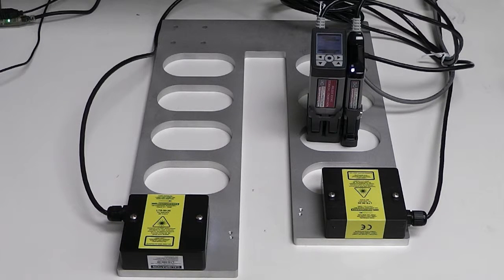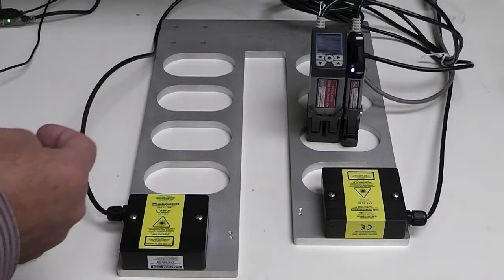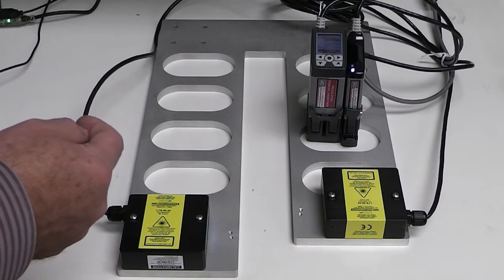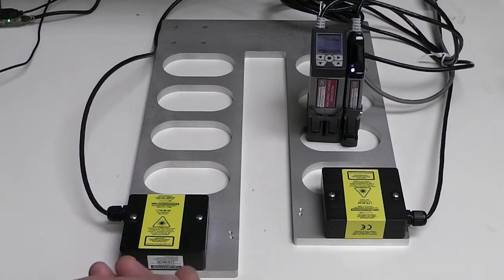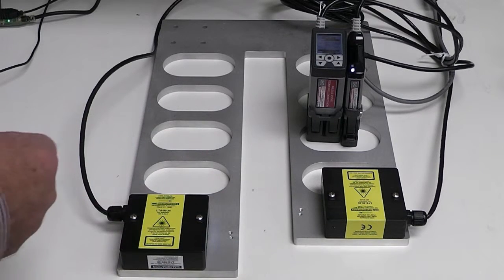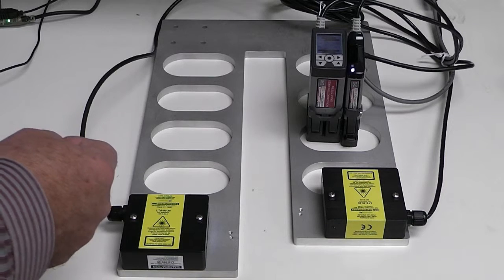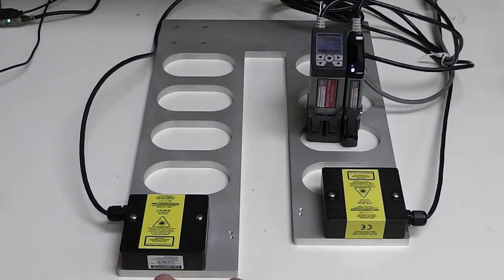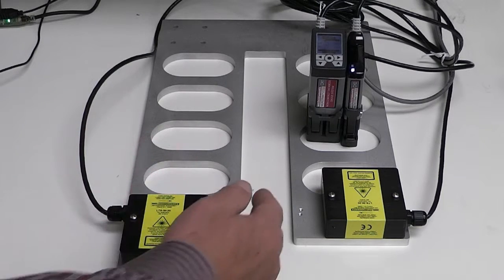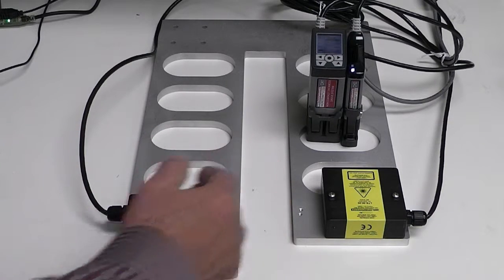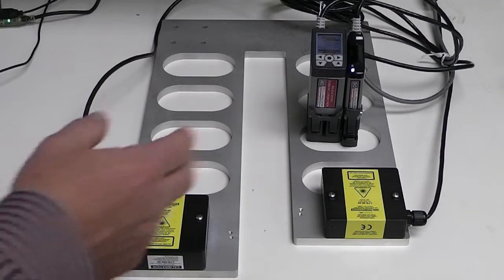The two other alarms out of the three digital alarms I have are set for a high alarm of 90 thousandths, so anything above 90 thousandths of an inch will trigger that. And out of range, which means that if nothing is in between the two heads we have a condition there.